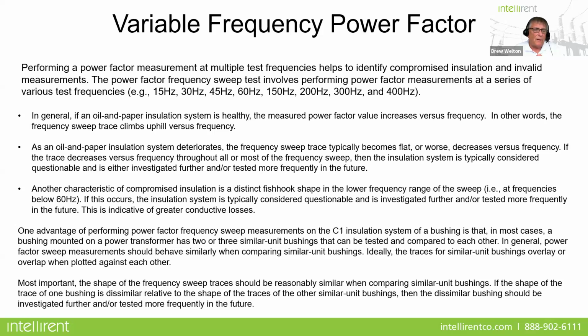and get measurements at these different frequencies. Because in general, if the oil and paper insulation system is healthy, the measured power factor value increases versus frequency. So in other words, the frequency trace climbs uphill versus frequency, and this is normal. But as your oil and paper insulation system deteriorates, the frequency sweep trace typically becomes flat or even worse, decreases versus frequency. So if the trace decreases versus frequency throughout all or most of the sweep, the insulation system is typically considered questionable and may require further investigation.